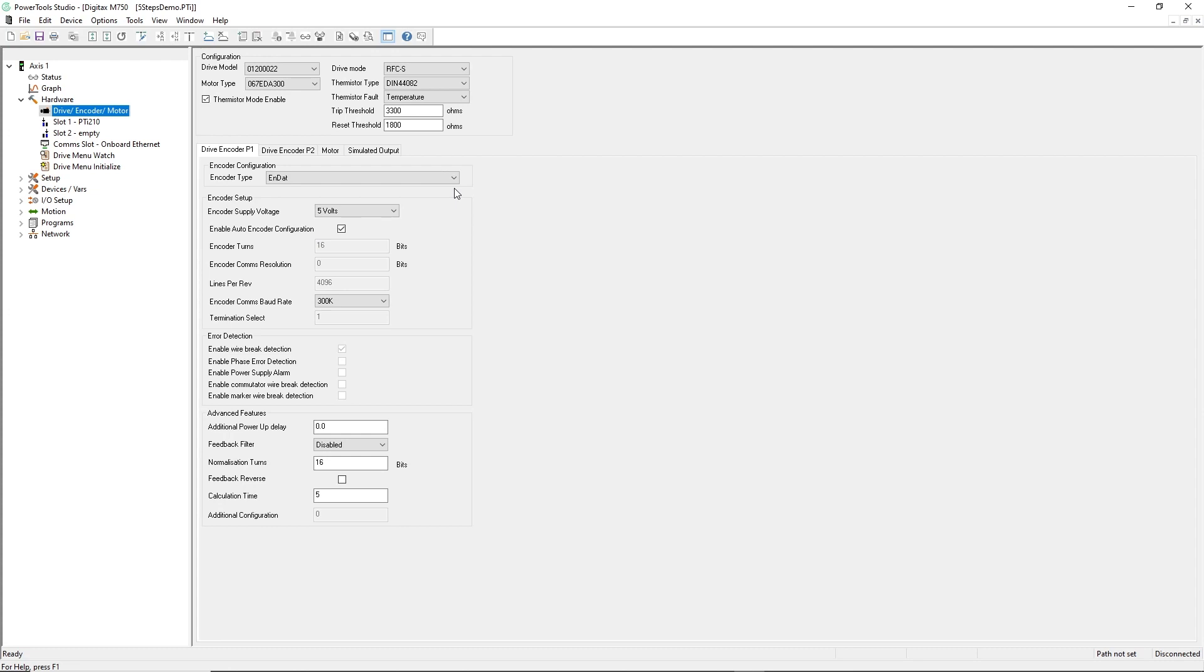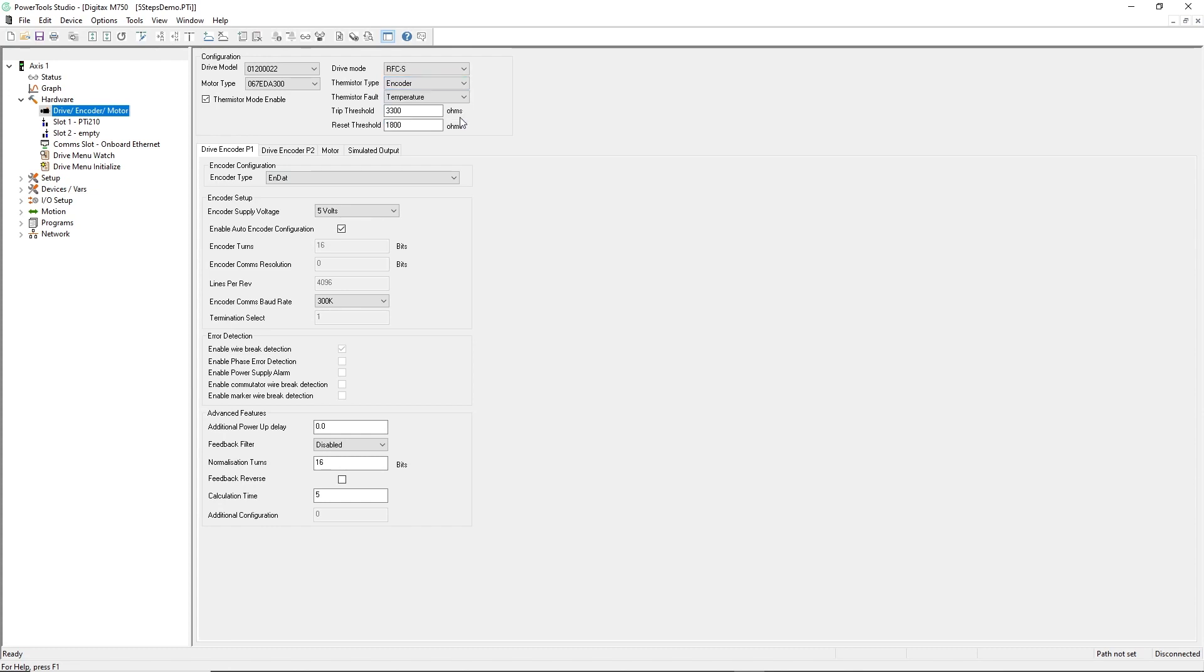Before closing this screen, and because I'm using an EnDat encoder, I'm going to specify the thermistor type to be encoder. The motor thermal information, when using an EnDat encoder, is included in the transmission between the drive and the encoder.